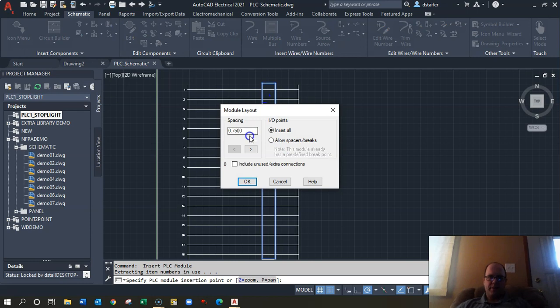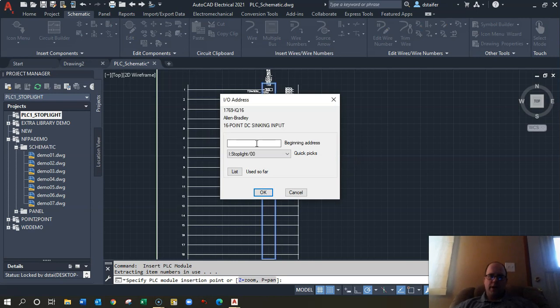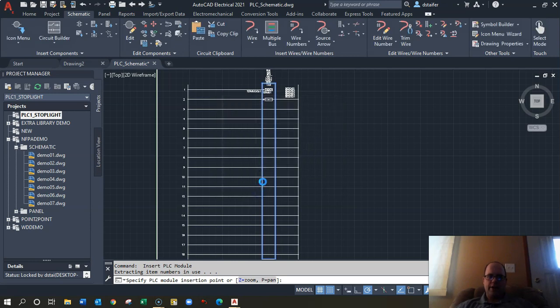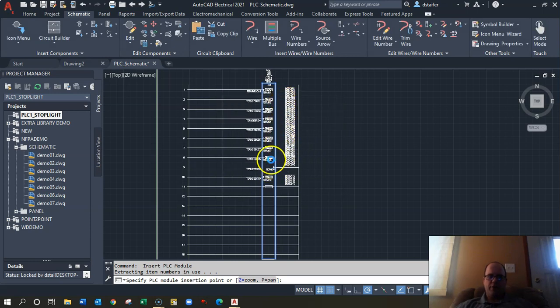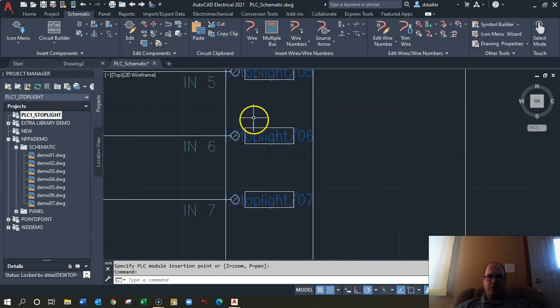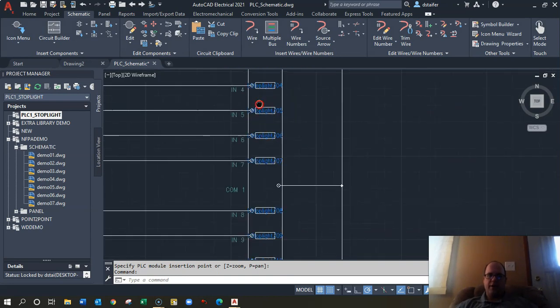It's going to ask for spacing — keep the default. Name the module 'Stoplight'. For beginning address, I'll do I:0 and hit okay. It will default everything for you. Do you want decimal or octal? Go decimal. If you scroll in you can see it gives you the tag name and everything already pre-addressed.